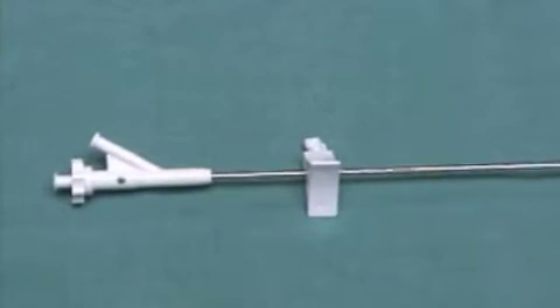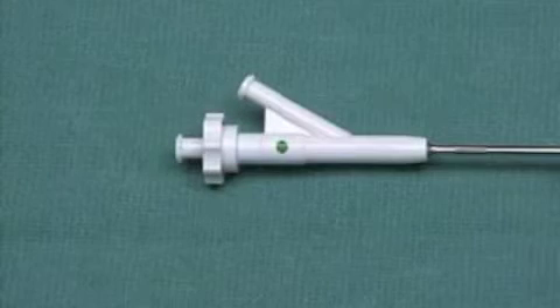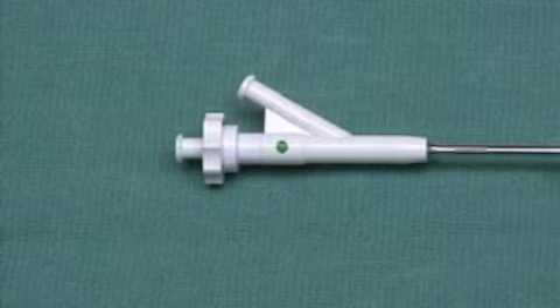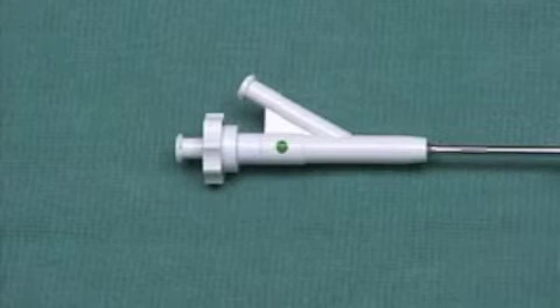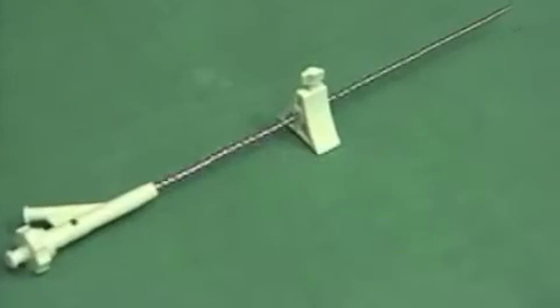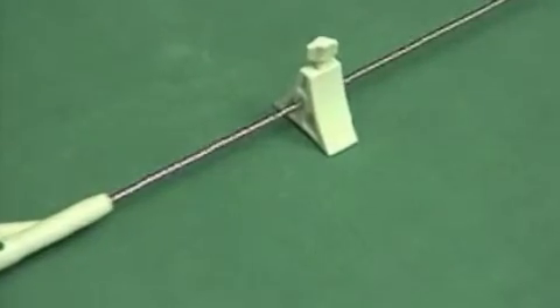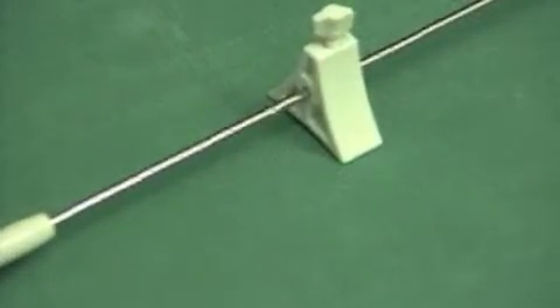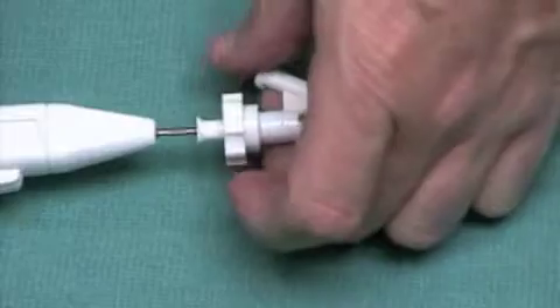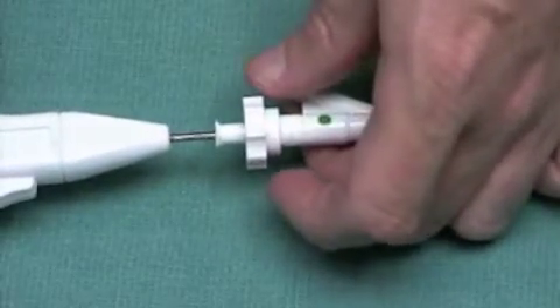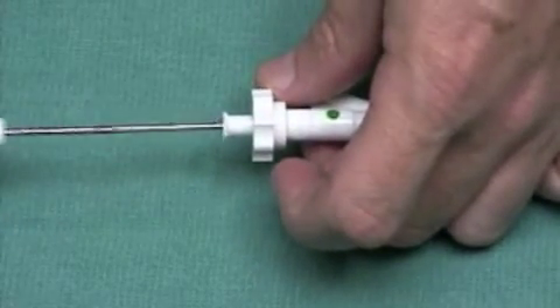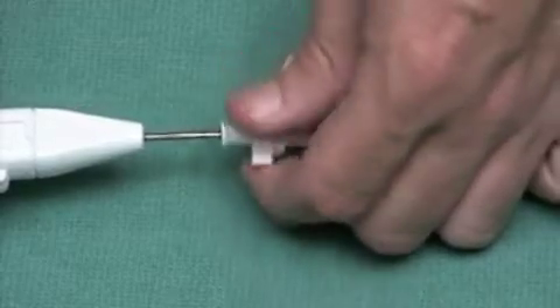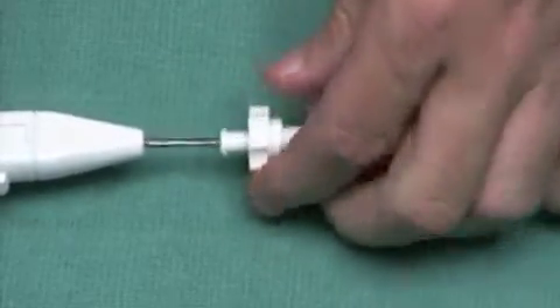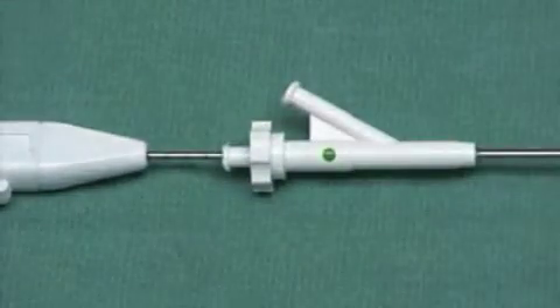The laser endoscope is placed into the disc through a working channel. Identify the working channel by its green dot. A triangular skin stop helps secure the working channel against the patient's skin. The working channel has an aspiration port for removing the saline irrigant. You can loosen or tighten the working channel's grip on the endoscope shaft by turning a compression fitting.